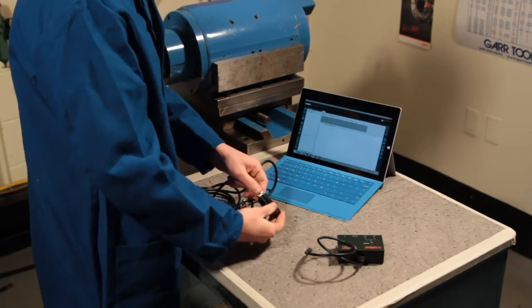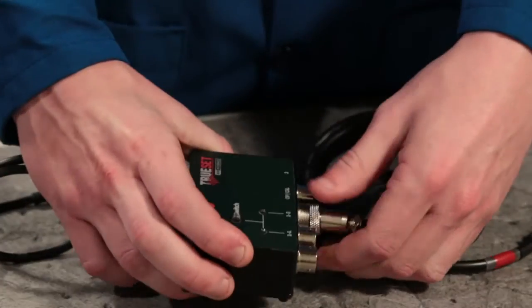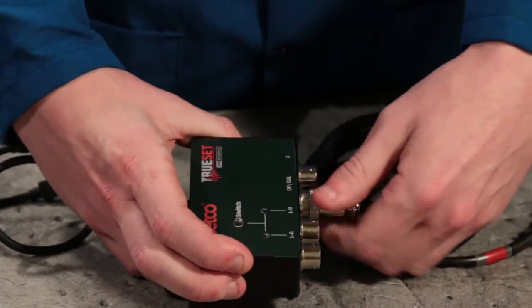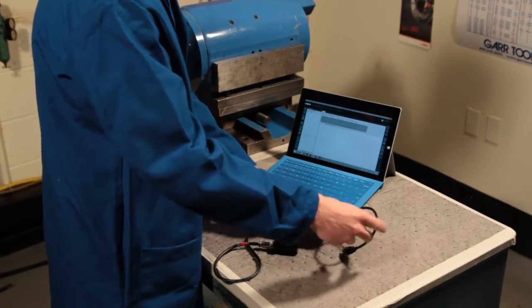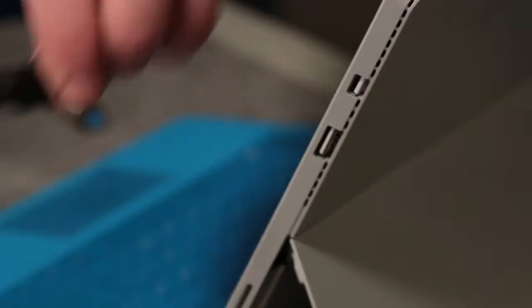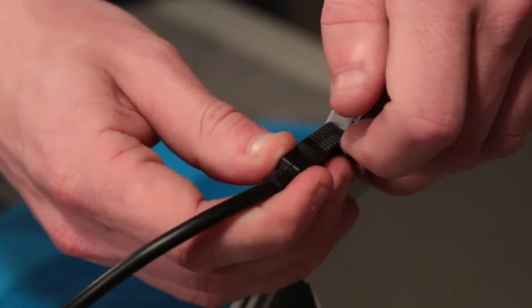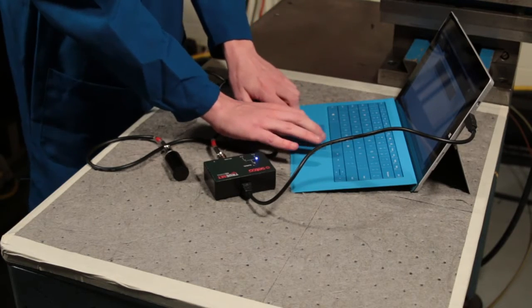Connect the calibration device to the end of your cable and the other end into the DAC box in the port labeled OP. Connect the DAC to your computer through one of the available USB ports. Note, it is important that this USB port must be connected to the DAC box when making all TrueSet measurements.